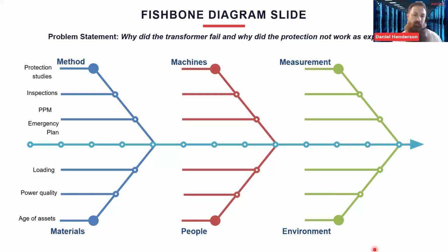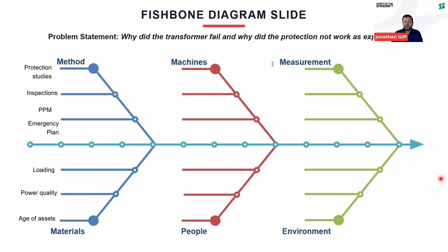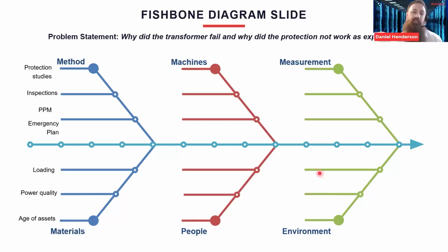Yeah, definitely. And again, just to add on to what Cody said, with most facilities, they start off at a certain size. And as production increases, as the company becomes larger, you often find that load is added to the network, and it's not always accounted for with regards to the rating of the equipment supplying the manufacturing process. So I would absolutely look at what the loading was for that transformer. Was it within its capability, or was it overworked? And if it was overworked, do we know how long it had been overworked for? Transformers do have a cyclic rating, but if that is exceeded with extensive additional load, then that will degrade the transformer over time. Digressing slightly, but that's an issue everywhere.